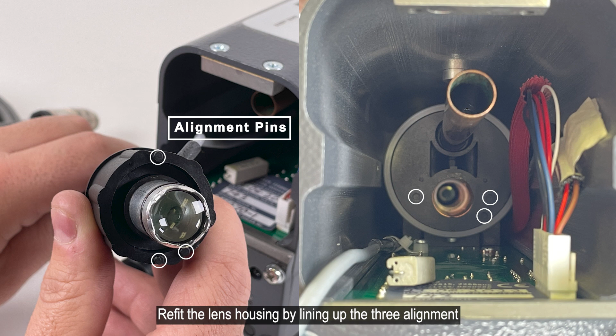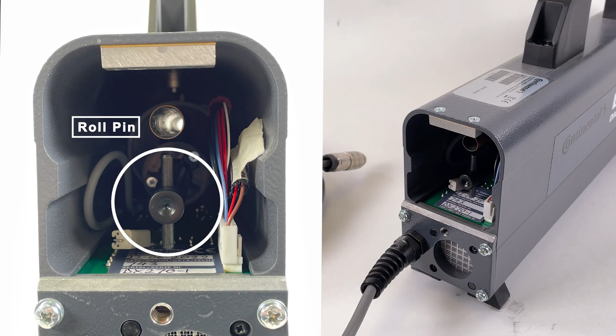Refit the lens housing by lining up the 3 alignment pins with the corresponding holes in the sampling tube. The lens is refitted correctly when the roll pin is vertical and it cannot be rotated. Refit the end cap and tighten the knurled knob. You are now ready to use your smoke meter.